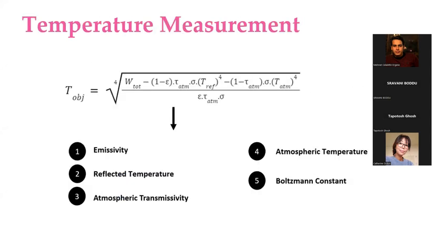Infrared thermal cameras internally use some parameters to construct the temperature of the target object by assuming some parameters. So let's go into details of these parameters, because it is important that we set these values to their true values. Otherwise, the temperature values we see might deviate from the actual temperature values.